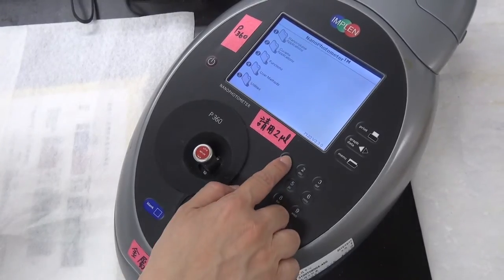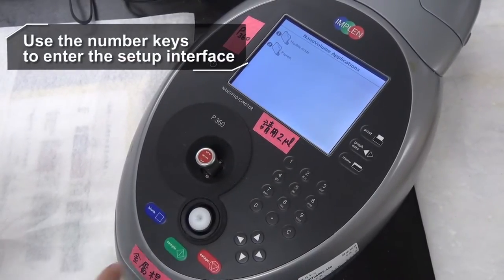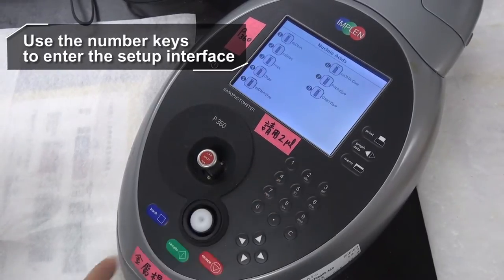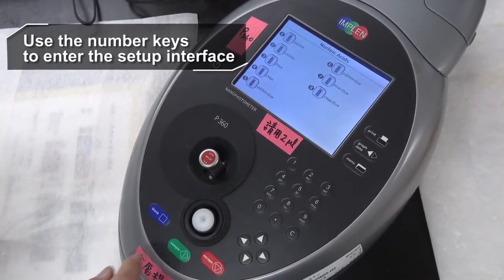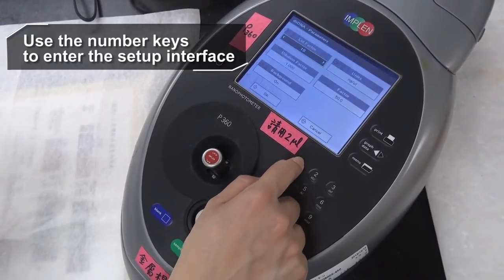8. Set up the parameters. Navigate the main menu using the number keys to enter the parameter setup interface for the sample type to be measured. For double-stranded DNA, pressing number 1 three times brings up the setup interface.